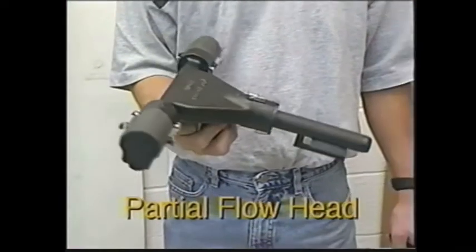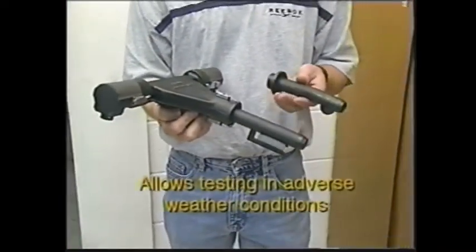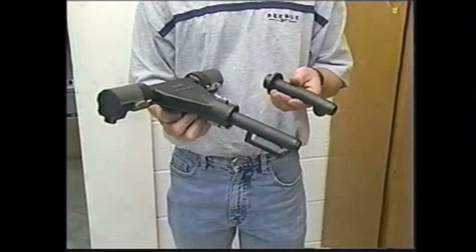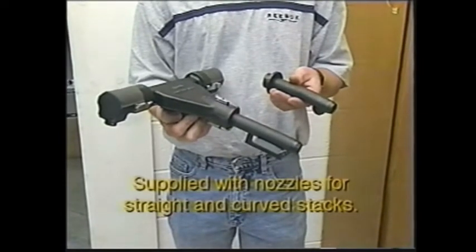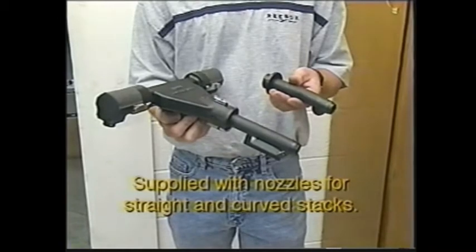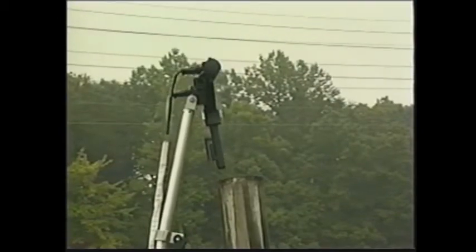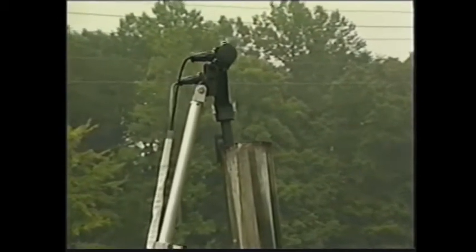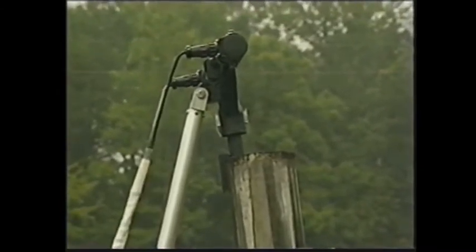We also offer a partial flow head. It allows testing even in adverse weather conditions. For the most accurate reading, it is supplied with nozzles for both straight and curved stacks. Attachment is simple. For either unit, keep cables away from hot stack.